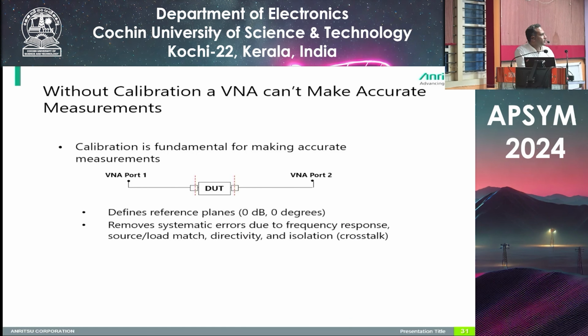So it defines a 0 dB and removes some of the systematic errors, such as frequency, load match, directivity and isolation. So these all come under the components that are used inside the instrument. Those errors will be removed when you do the systematic error correction. Okay. These errors are contributed from the instrument.